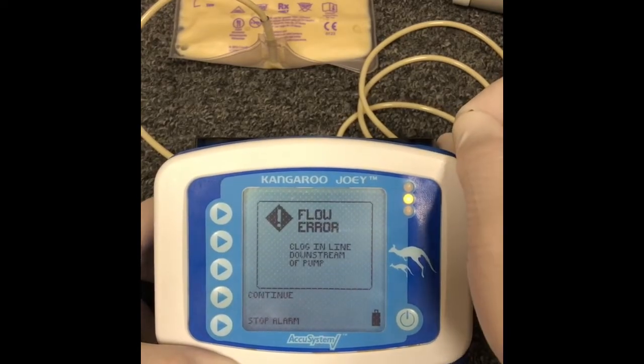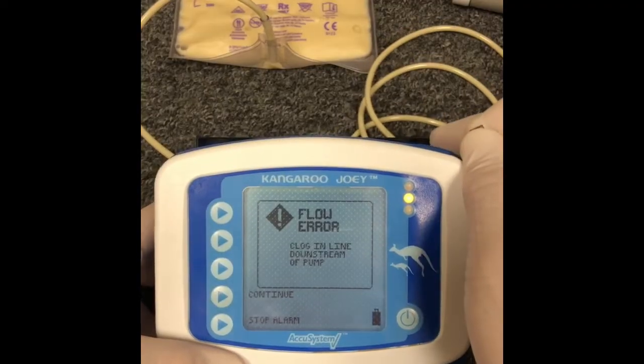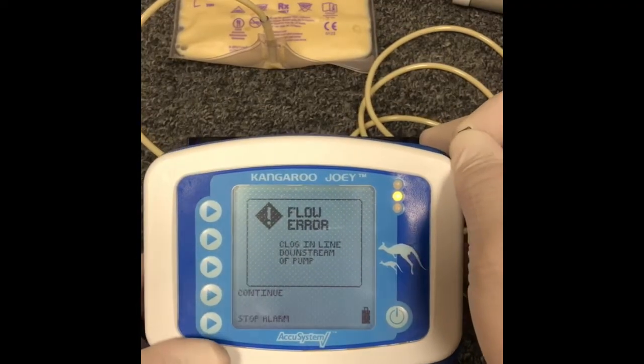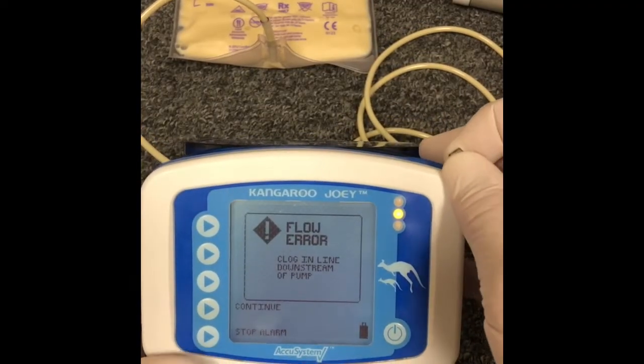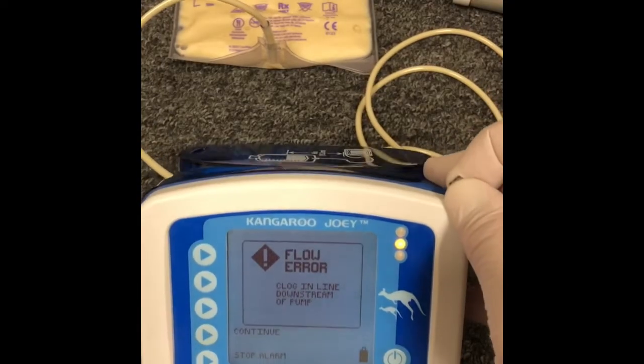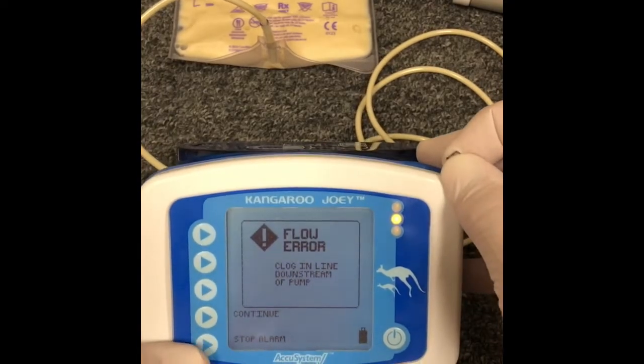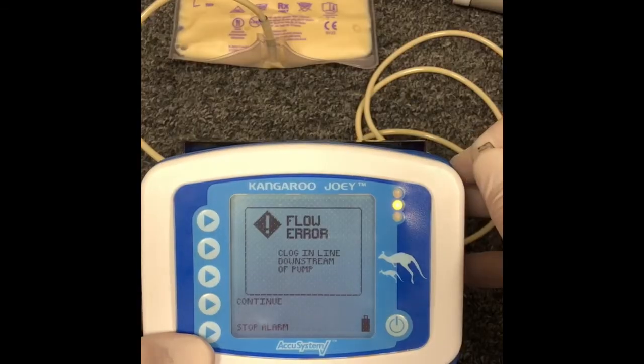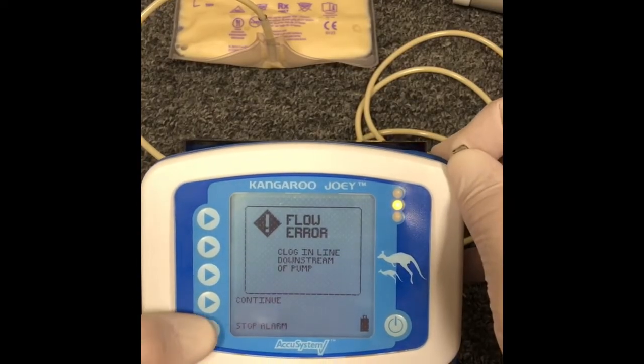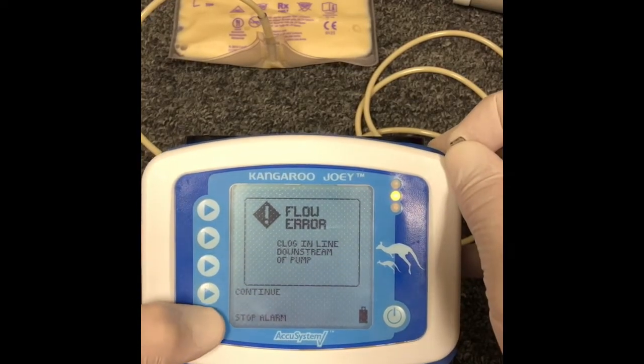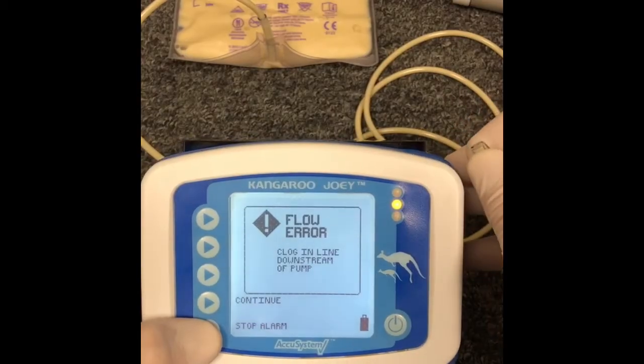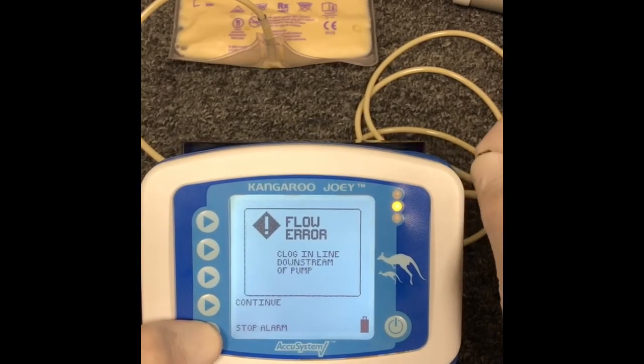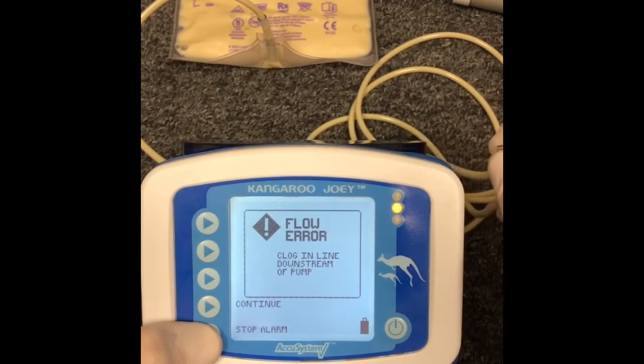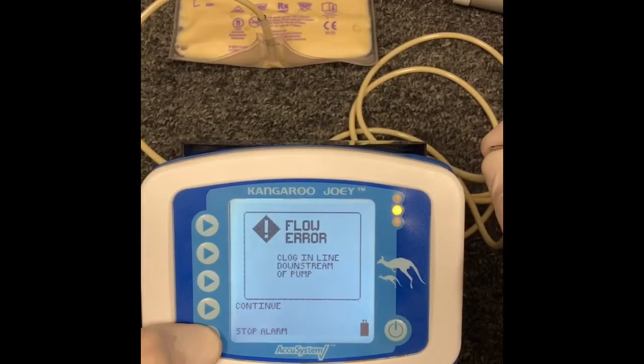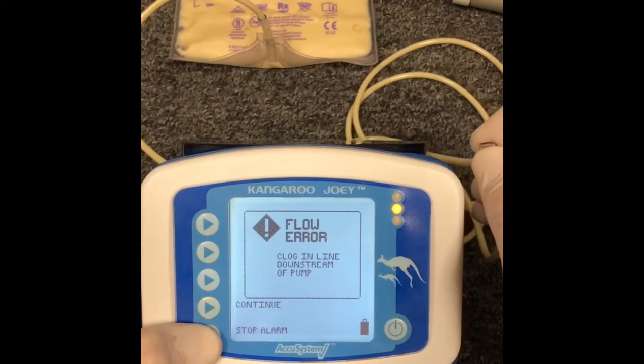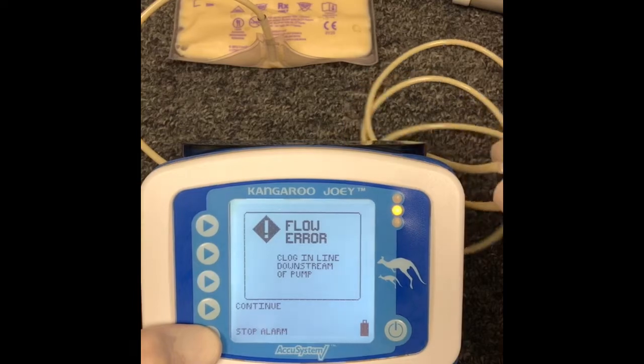There we go. As you can see, we now have a flow error alarm. It is basically beeping us saying, hey, somewhere down the line there's a clog. I need you to figure out what's going wrong, fix that, and then I can get running again. I'm gonna go ahead and pause it so it stops beeping. I just wanted you to see what that alarm is. So let's do stop alarm. There we go. Basically, if there's an occlusion down the line, the tubing got pinched, the patient's G-tube is stopped up, whatever it is, this pump will say, hey, there's no flow going on, fix it.